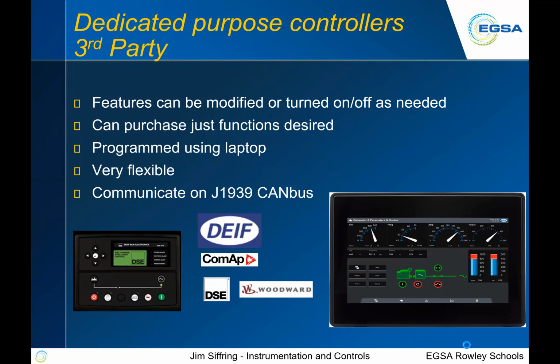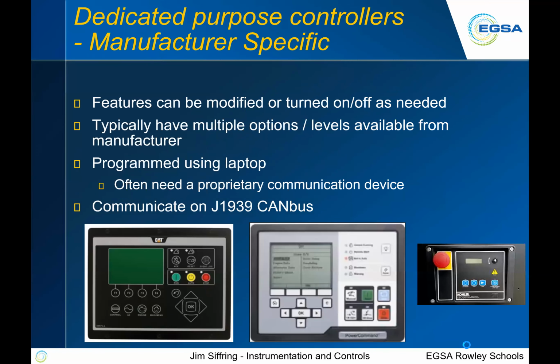You can often program them with a laptop. They're very flexible. They communicate over the CAN bus, over the J1939. Very powerful. And then you get into manufacturer specific stuff, which is very similar to the previous. Typically, on the left, you see a Cat, the center is a Cummins, the right one is a Kohler. So this is what would come on one of those gensets from the factory. Again, typically, you program them with a laptop. You need a communication device, like we discussed at the very beginning of this module. And again, they communicate over that same J1939 CAN bus.